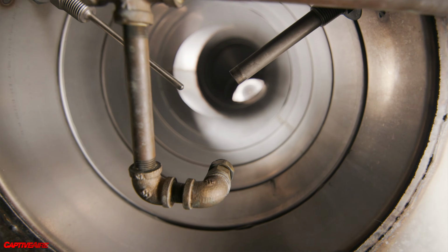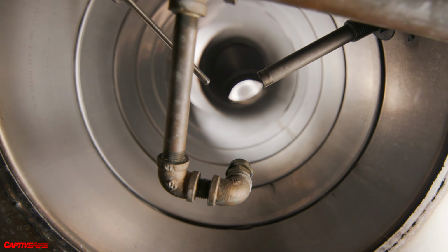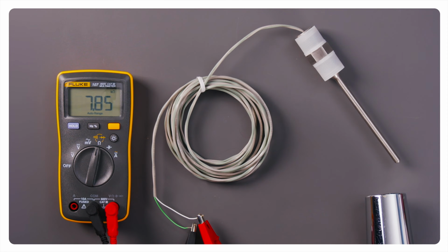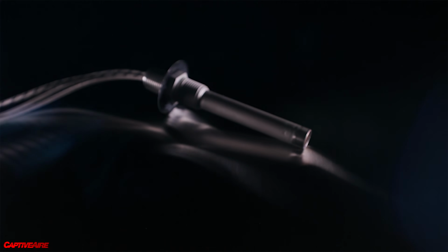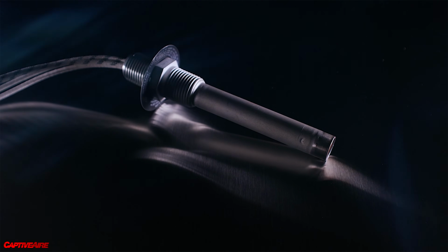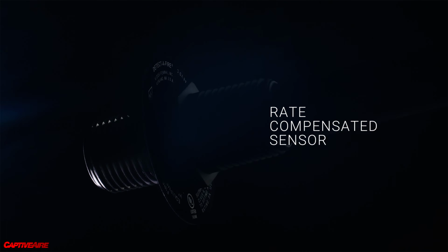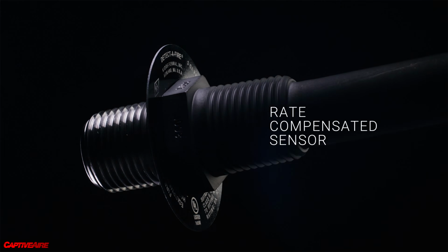There's a couple different types of sensors that we use for detection. One is we can use an absolute temperature. So if the temperature goes above X, we activate. There's also another type, and that's rate of rise, which will detect a certain increase in temperature over time. And some sensors, like the one we use, do both, and it's called a rate compensated sensor. So it will detect an absolute temperature, but it will also detect a rate of rise. And it does this with two mechanical features built into the same sensor.